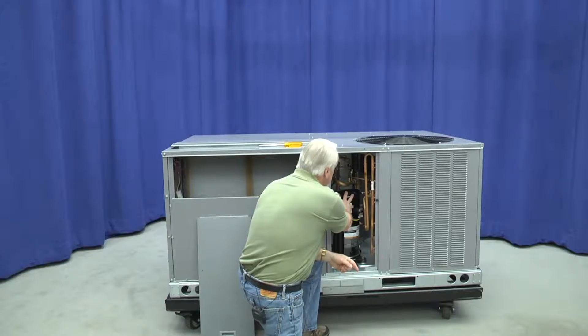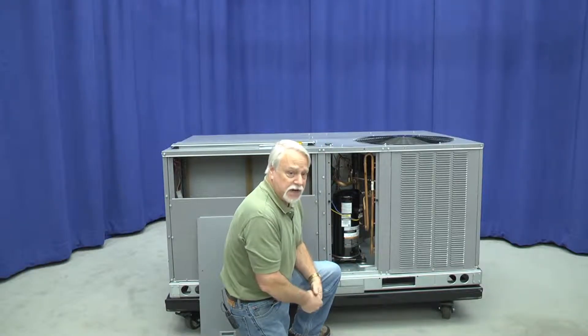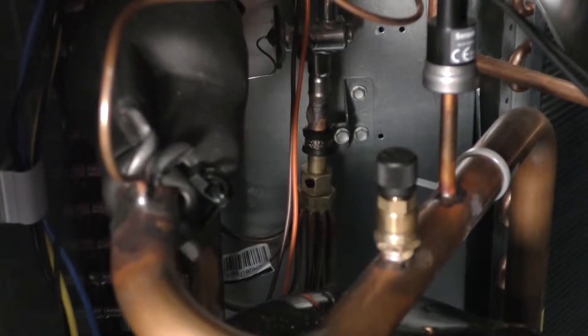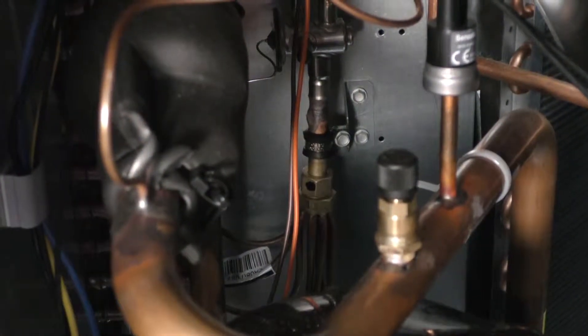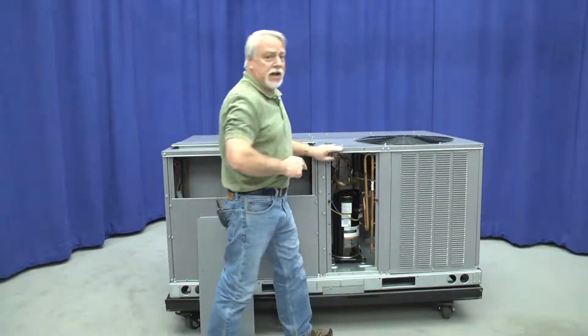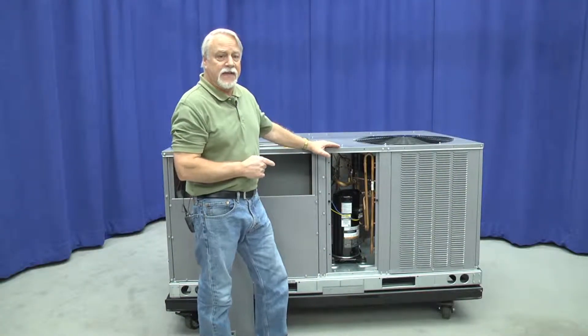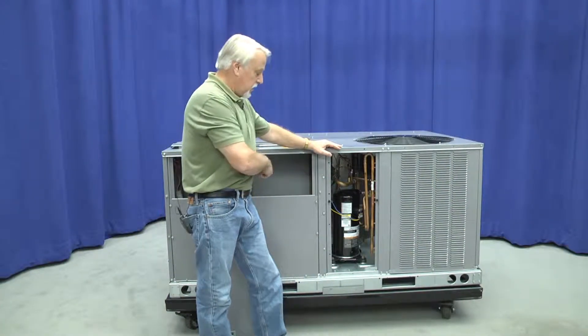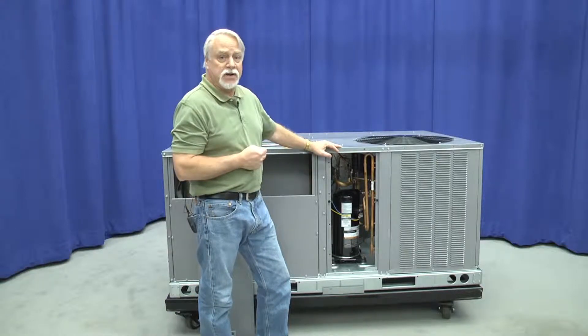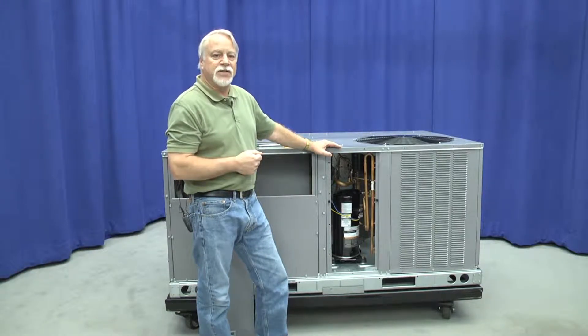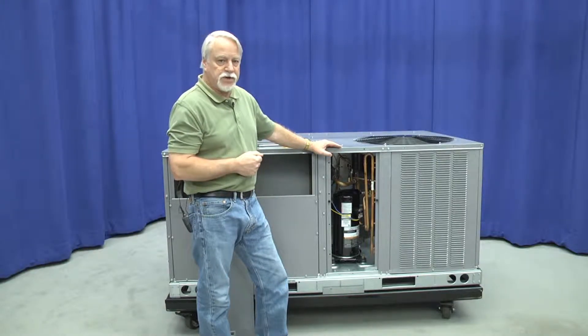Notice this particular unit has a TXV type refrigerant control system. Follow the charging table or charging chart that is on the panel on that particular machine to confirm that I've got the right refrigerant charge.